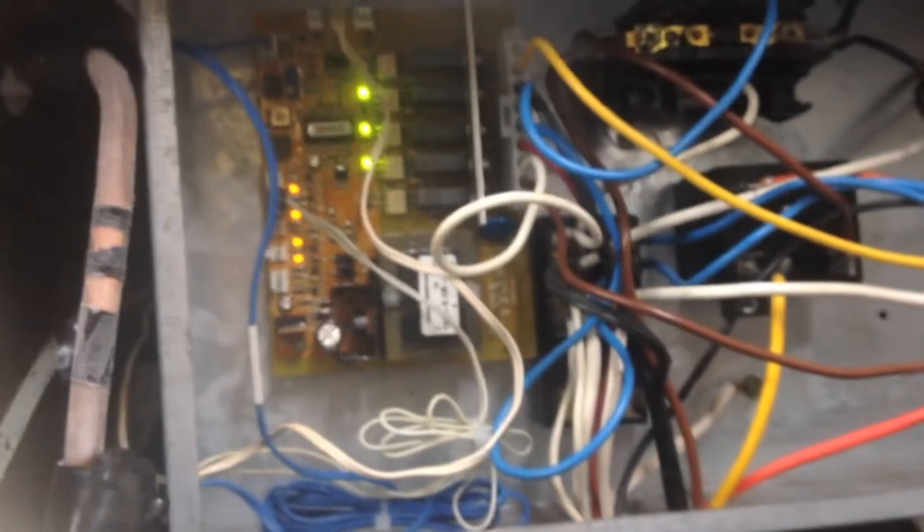This is where the ice is made — you get a tube here and it just circles down through that pipe there. This is the board I'm going to be working with regarding the time it takes to make the ice. My water temperature here is about 40 degrees right now. I'm going to let this unit run a little bit longer.